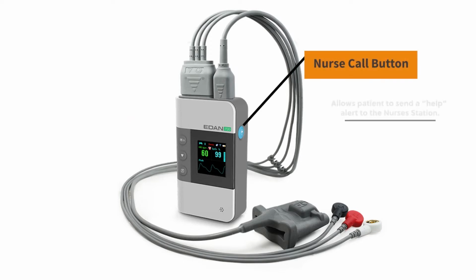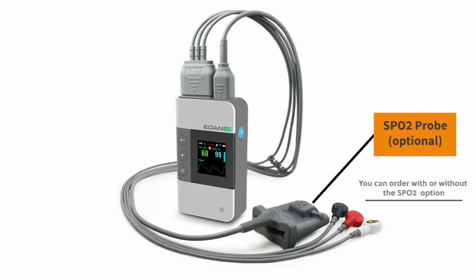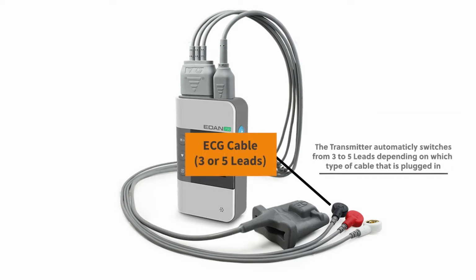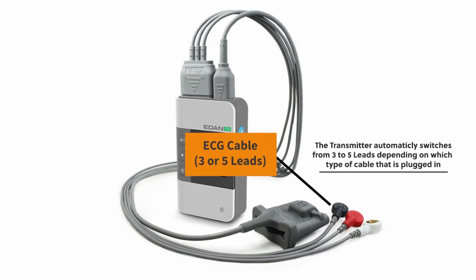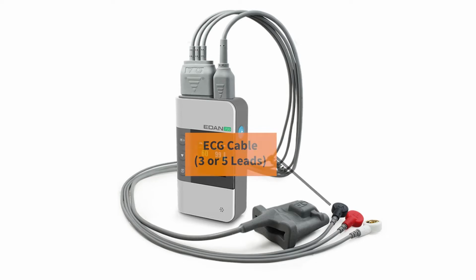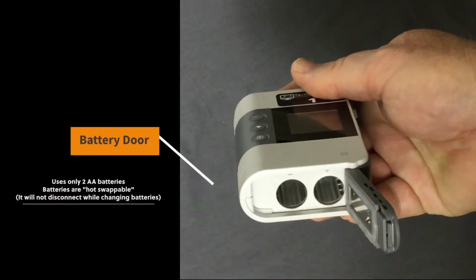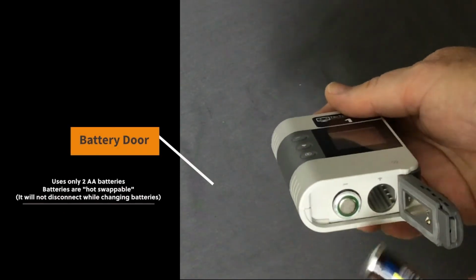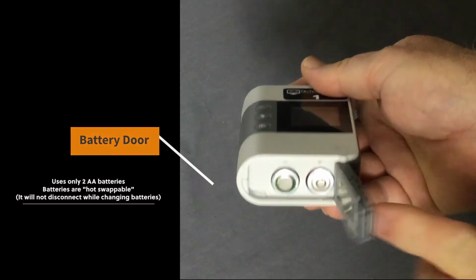The button on the side is the nurse call button. This button allows the patient to send a help alert to the central station. This is an SpO2 probe and cable. This cable is optional. The IT20 telemetry transmitter can be ordered with or without SpO2. This is a 3-lead ECG cable. You can also use a 5-lead cable if you choose. The IT20 telemetry transmitter can sense the type of cable that plugs into it, and configures the correct cardiac leads. And on the bottom, we find a latch door that holds the 2 AA batteries that power this transmitter.